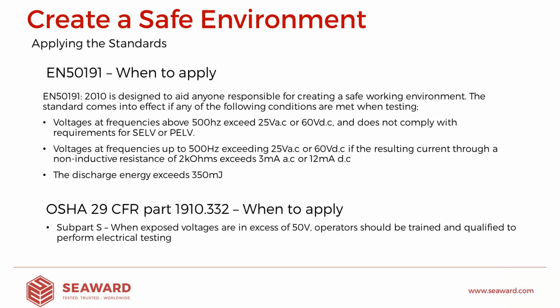So we can take into account the level of test, but we should also look for the level of current the tester is capable of. And under fault conditions, could that tester potentially, if someone changed the test sequence, deliver the full amount of current that is potentially available to it? And if that answer is yes, then we really should be looking to create a safe working environment.